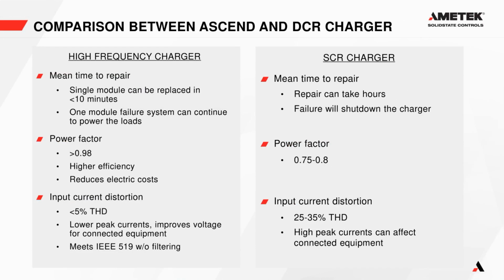So the differences between our Ascend high frequency charger and the DCR SCR based charger that we have been selling for 15 years or so. The biggest advantage of the Ascend is the mean time to repair is less than 10 minutes, and you can have redundancy built into your system if you're not operating at full load. It also has a better power factor of greater than 98%, better efficiency, which will reduce your electrical costs. The total THD input distortion is less than 5%. Compare that to DCR, which is somewhere around 25 to 35% without our input filter.